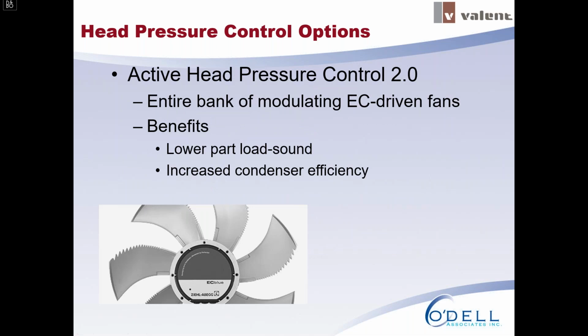So this option is where you have an EC motor on all condenser fans, and they modulate up and down together. So you get better part load sound performance. It's very, very quiet at part load, and increased condenser efficiency. So if all of your fans are modulating up and down together, you're always going to have even airflow across the whole condenser coil. And you're also not going to have backdraft through fans that are off. So this is the most efficient and quietest option, but it's also the most expensive by, you know, a marginal amount. So there are pros and cons, but for performance and sound, this is definitely the best option.